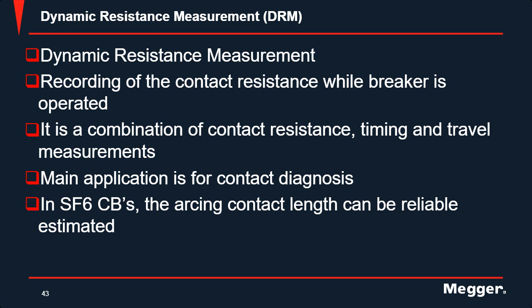With the DRM measurements, the arcing contact length can be estimated. The only alternative to figuring out the length of your arcing contact, how much life it has left in it, would be to dismantle the circuit breaker and take a look for yourself with a visual inspection. In the case of the SF6 breaker, the arcing contact is commonly made out of tungsten, and the contact slowly burns off and becomes shorter with each interruption of the load current. So every time you operate that breaker under load and there's an arc between the contacts, you're slowly diminishing the life of that arcing contact. The only way to figure out the length of that arcing contact is to do a dynamic resistance measurement, or to open up the breaker and take a look inside the interrupter.